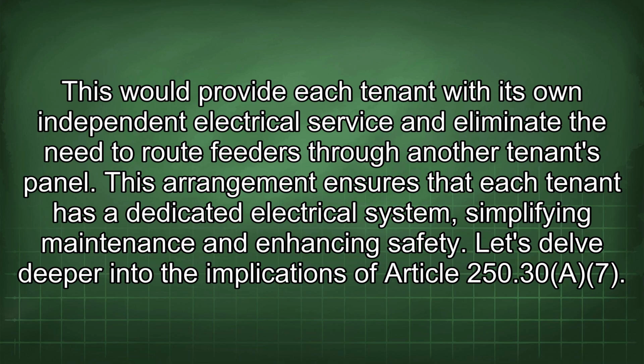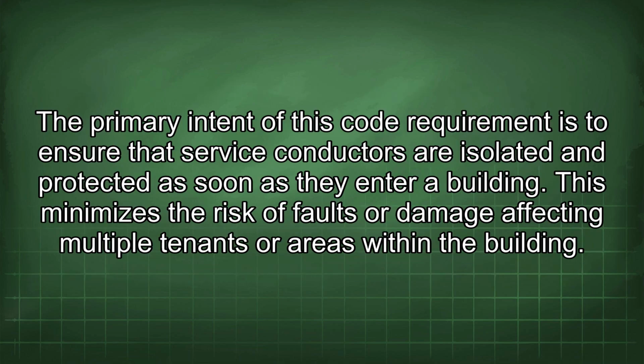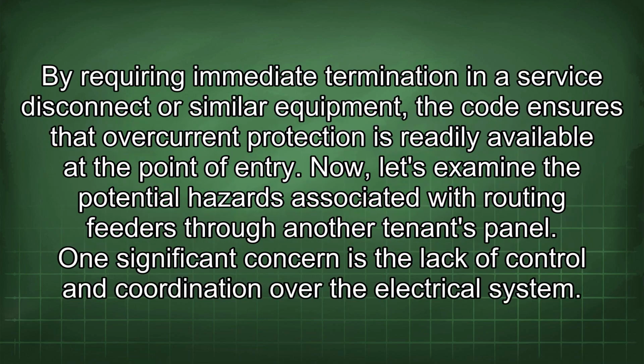Let's delve deeper into the implications of Article 250.30(A)(7). The primary intent of this code requirement is to ensure that service conductors are isolated and protected as soon as they enter a building. This minimizes the risk of faults or damage affecting multiple tenants or areas within the building. By requiring immediate termination in a service disconnect or similar equipment, the code ensures that overcurrent protection is readily available at the point of entry.